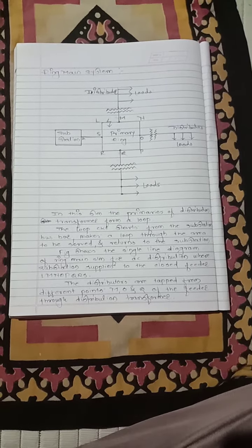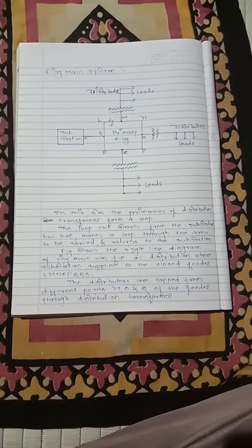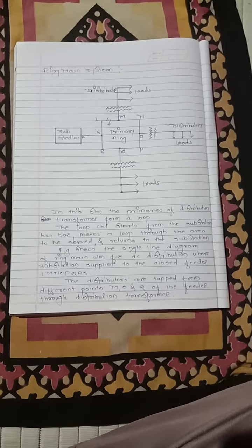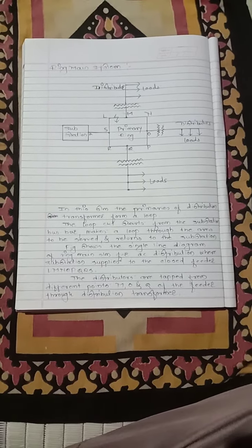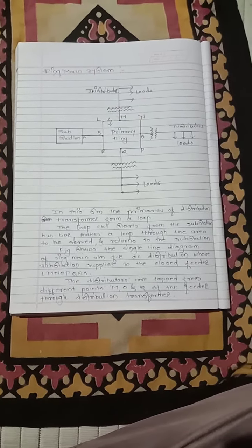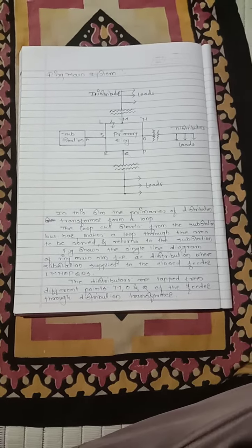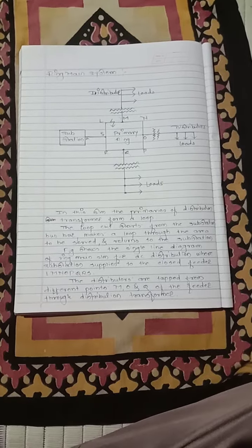The advantages of the ring main system are: it has less voltage fluctuation at the consumer end; second, the system is reliable because each distributor is fed via two feeders; third, in the event of a fault on any section of the feeder, the continuity of supply is maintained.